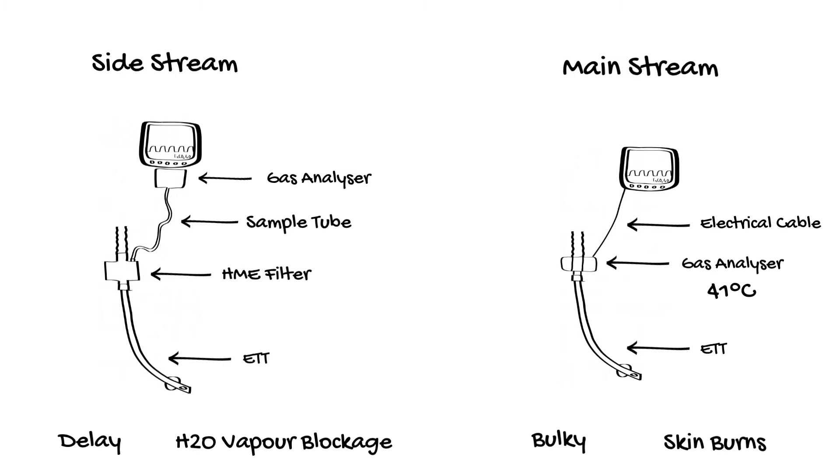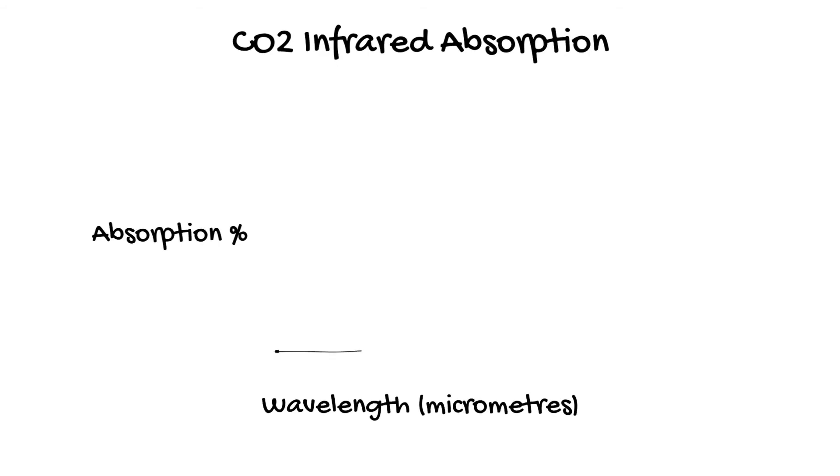Regardless of the sampling method, the gas analyser itself is basically the same. It relies on the principle that molecules with two or more types of atoms absorb infrared light at characteristic wavelengths. Carbon dioxide absorbs infrared light with a wavelength of 4.26 micrometres.